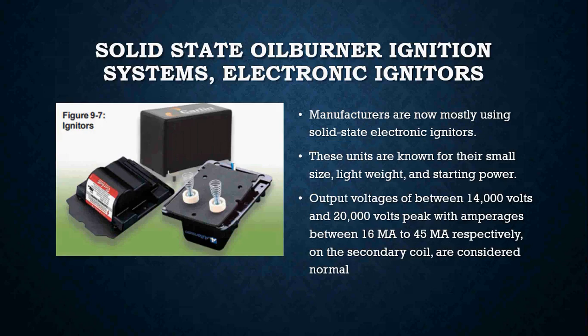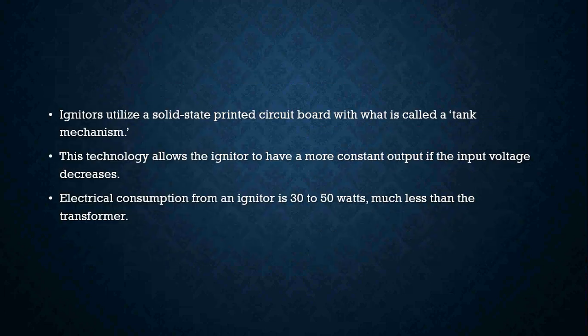Solid-state oil burner ignition systems, your electronic igniters, are a lot more common today. The reason is that they are smaller, lightweight, and have much larger starting power. The output voltage is anywhere between 14,000 and 20,000 volts, with an amperage reading of anywhere between 16 milliamps and about 45 milliamps on that secondary coil. Anywhere in that range is considered normal.